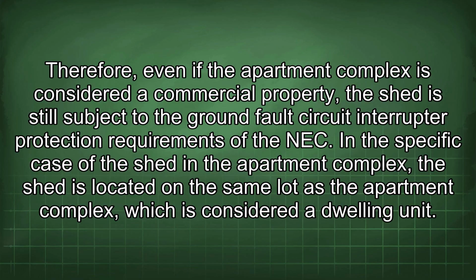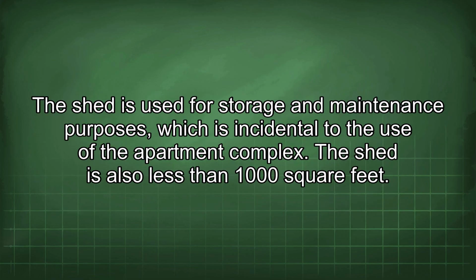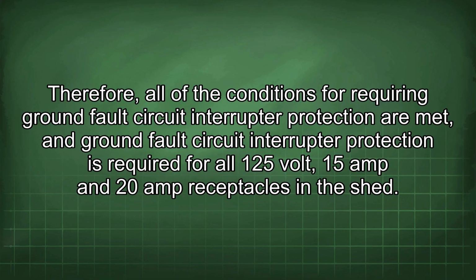In this specific case of the shed in the apartment complex, the shed is located on the same lot as the apartment complex, which is considered a dwelling unit. The shed is used for storage and maintenance purposes, which is incidental to the use of the apartment complex. The shed is also less than 1,000 square feet. Therefore, all of the conditions for requiring ground fault circuit interrupter protection are met, and ground fault circuit interrupter protection is required for all 125 volt, 15 amp and 20 amp receptacles in the shed.